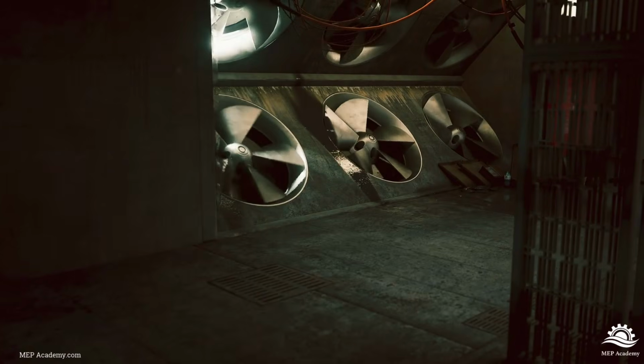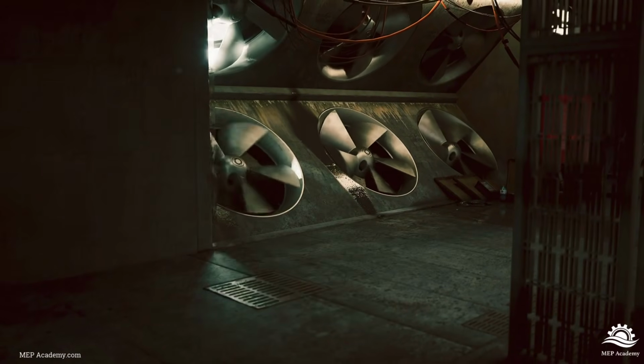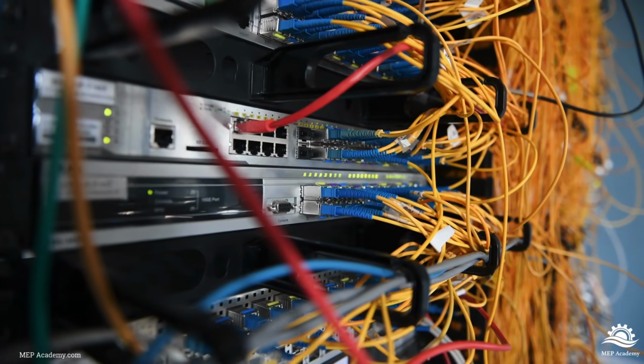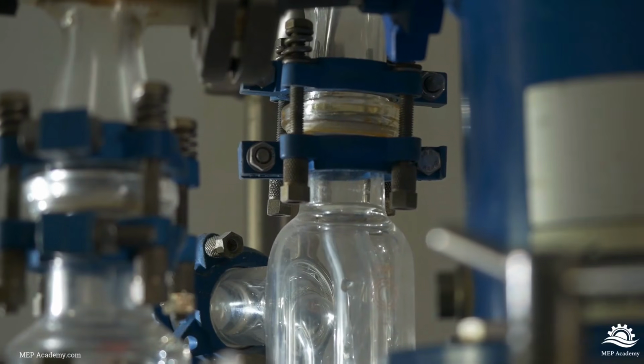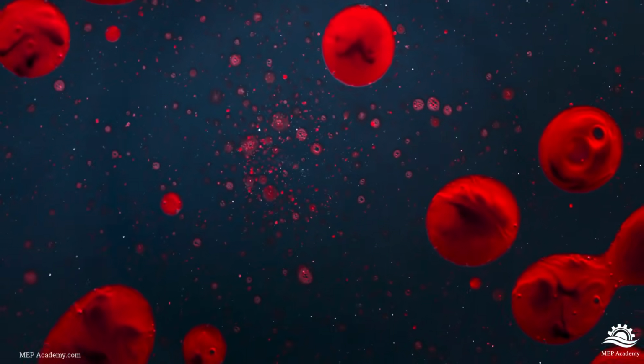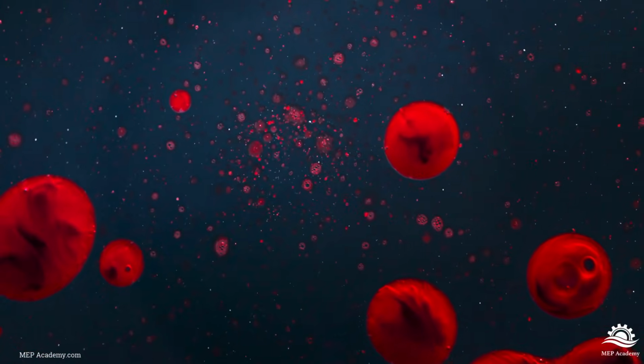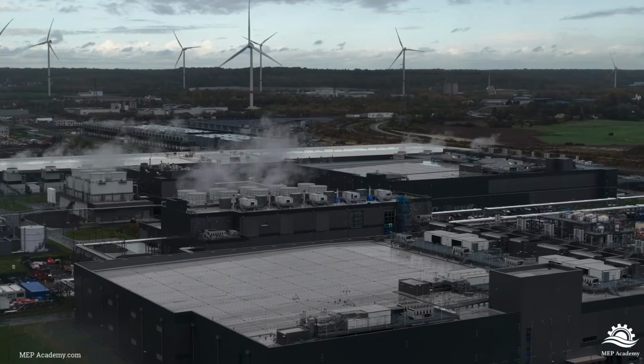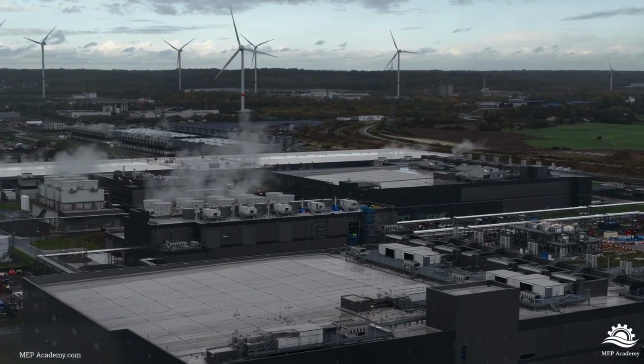At some point, air simply becomes inefficient. You can only push so much air through a room before energy consumption, noise, and infrastructure complexity become enormous. Moving air is difficult. Moving liquid is much easier. In fact, liquid can transfer heat thousands of times more effectively than air. And that's where immersion cooling enters the picture.